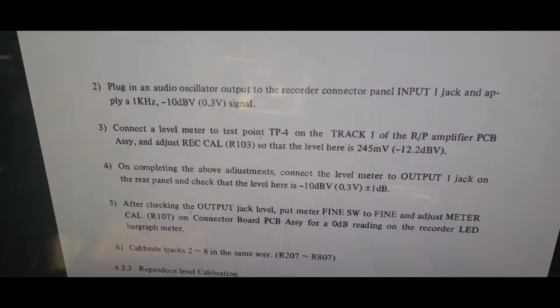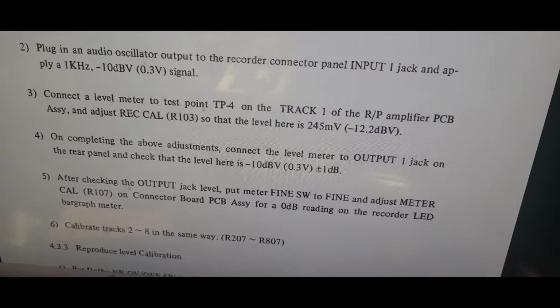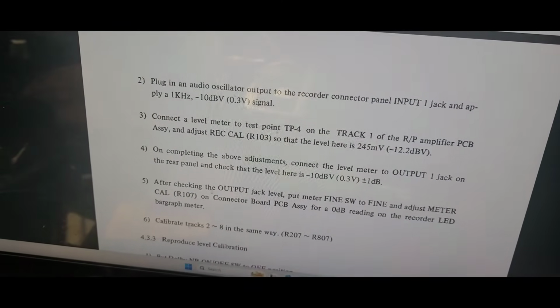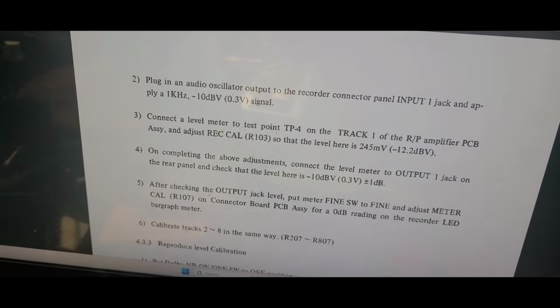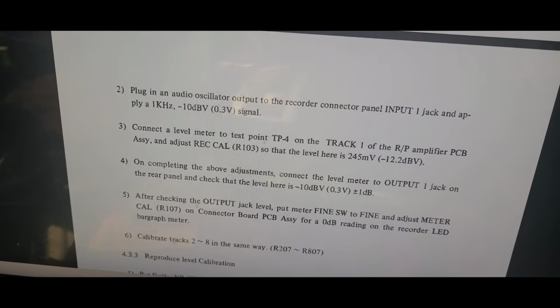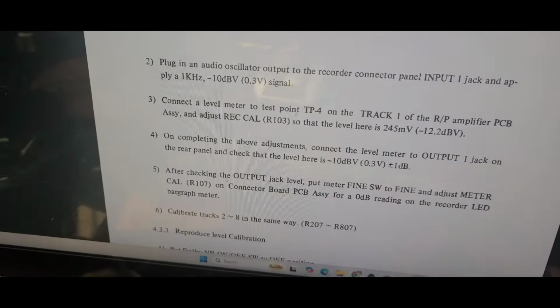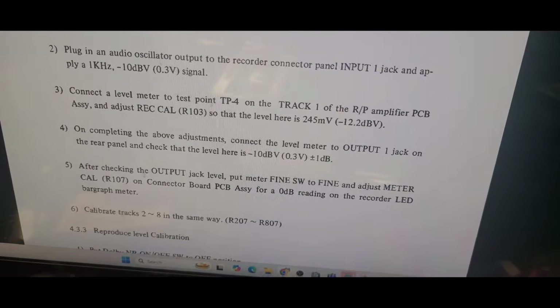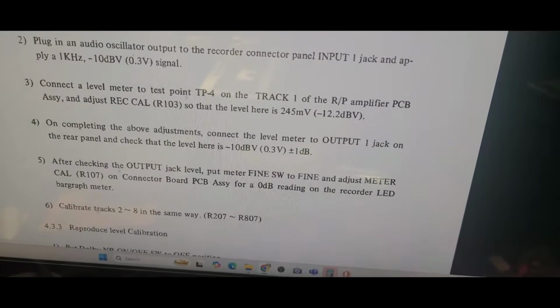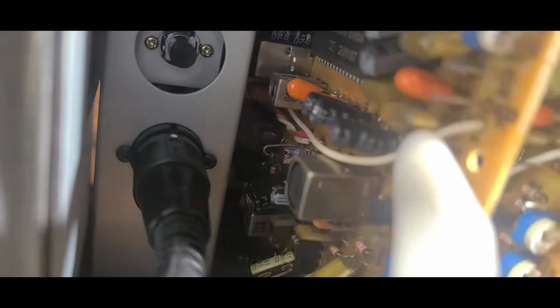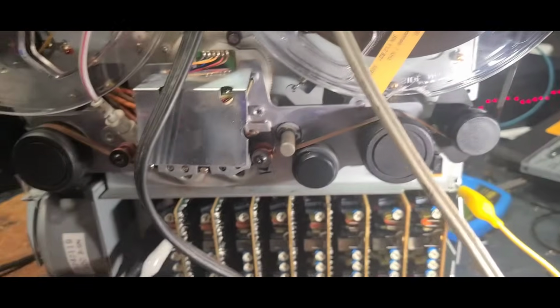So the procedure tells us to monitor test point 4 on track 1 with that negative 10 dB signal going in, and we calibrate or adjust that level at R103 to where we read 245 millivolts at test point 4. Test point 4 is located, if you can see it, back here. I've got where that white alligator clip is connected.